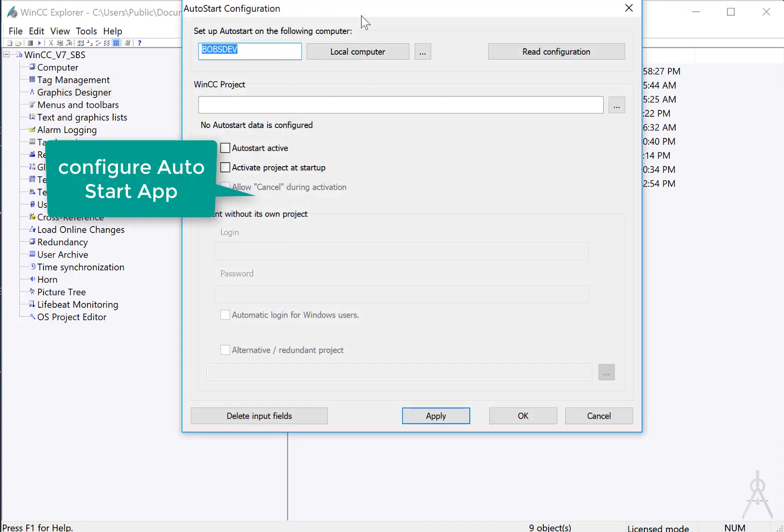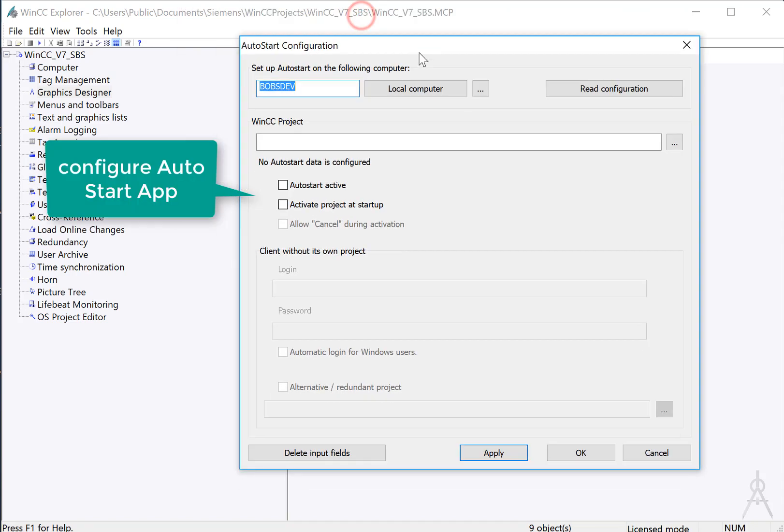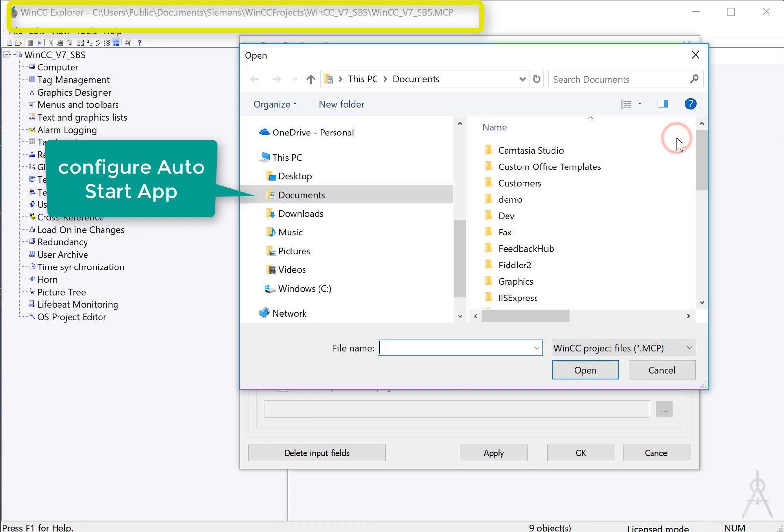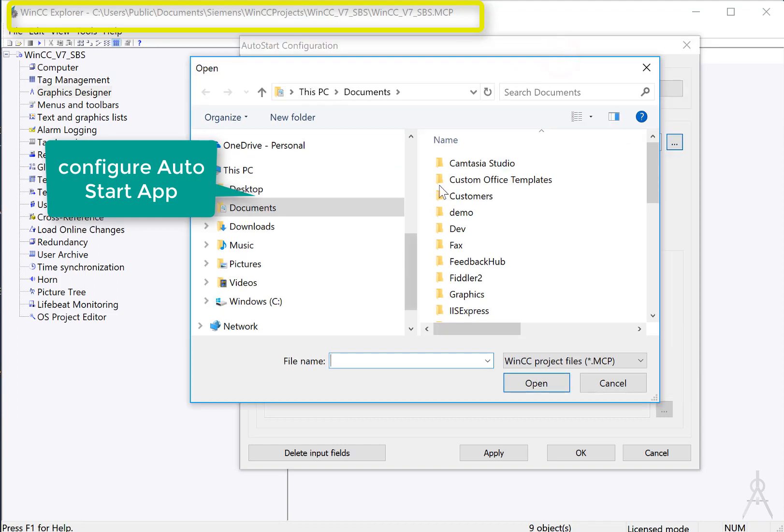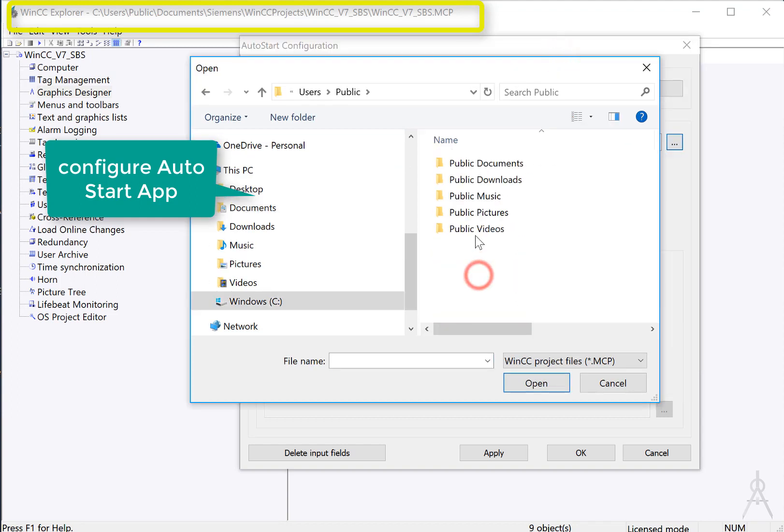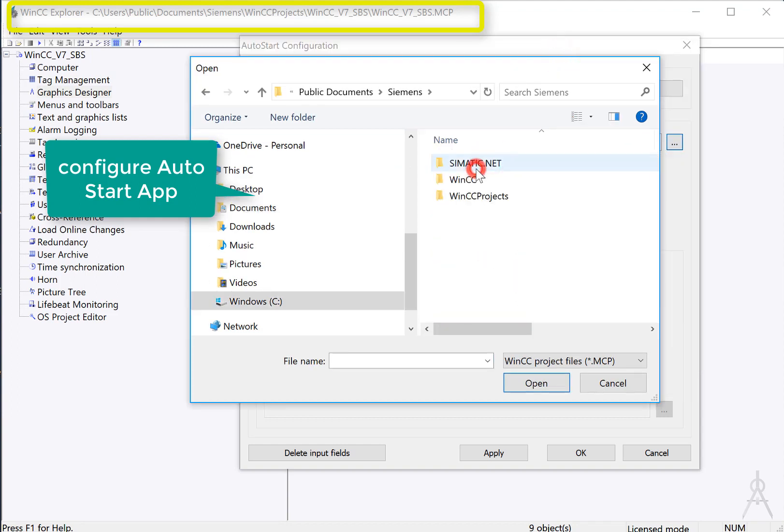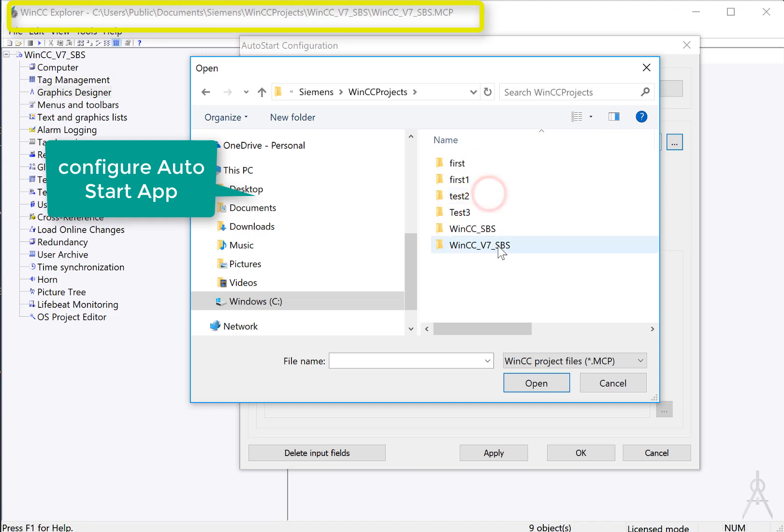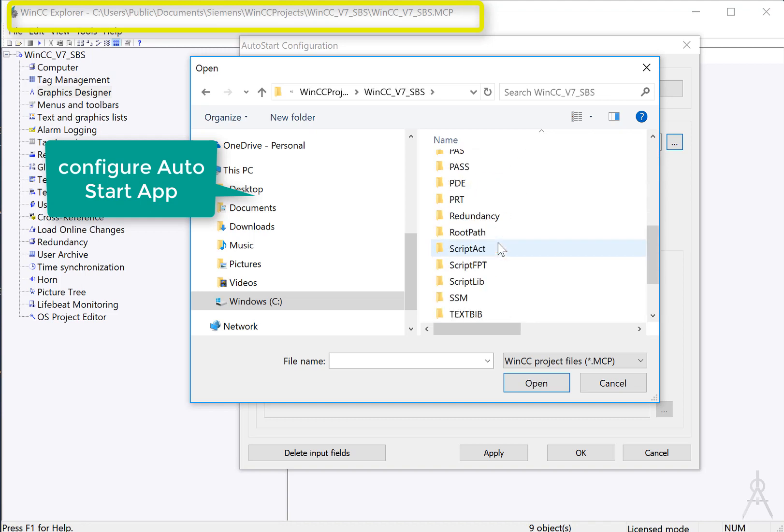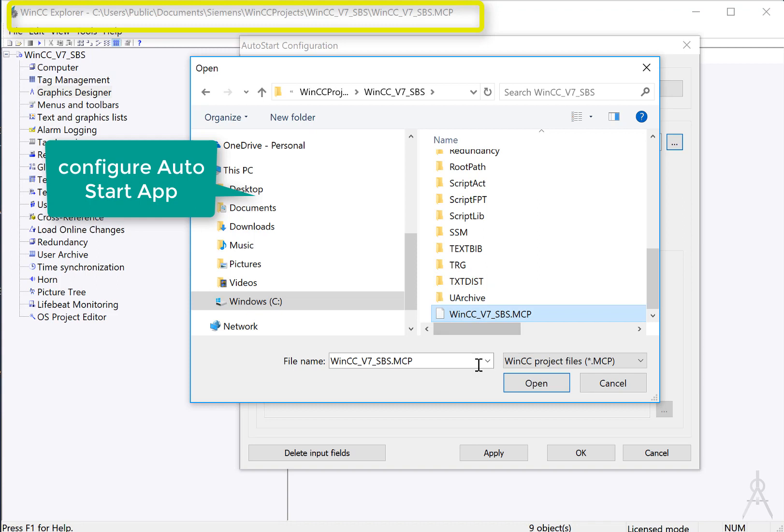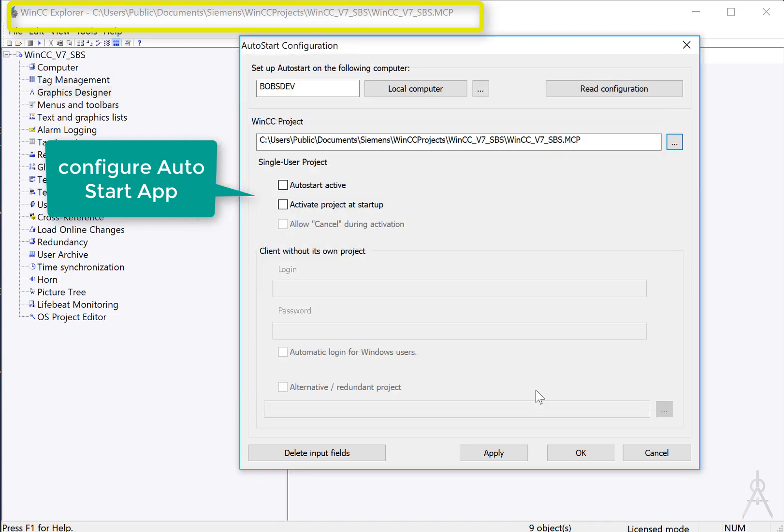You can also use the Siemens Auto-Start configuration to automatically start your project to runtime when the computer is rebooted. You just need to search for your project, select your project file, and then turn on Auto-Start Active and Active Project at Startup. If you don't want the user to be able to cancel this activation, then don't check this.